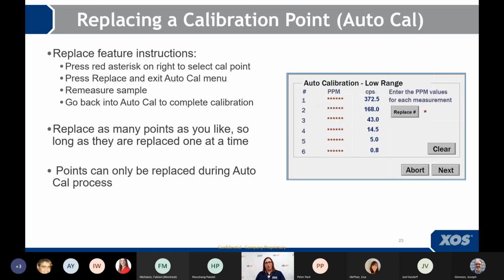Now I'm going to proceed to talking a little bit more about AutoCal. Most of you already know how to do auto calibration, so I'm not going to go through that. If you need some more information, drop your name in the chat, and if there's some time at the end, we can review the auto calibration. But in theory it works like this. You run a series of 6 samples. And then you go into auto calibration, which is this menu here in the picture, and you tell the analyzer what those calibration points are. The first sample that you ran will be in position 6, and the last sample that you ran will be in position 1. On the right is the CPS, counts per second value, which is your total counts divided by your measurement time. You simply enter the concentrations, and the analyzer does all of the calibration for you.